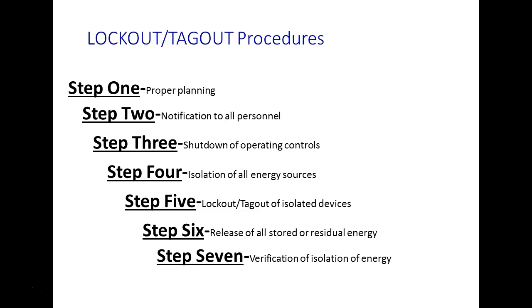When dealing with multi-phase systems, you need to go out there and check it, because you could go in and hit a button and one phase might still be stuck on. The machines might not run because they don't have enough energy to run, but there's still enough energy out there to kill you if you get into it. So on electricity, we get our meter out and verify that it's down.